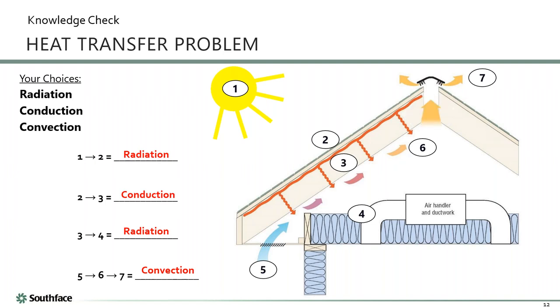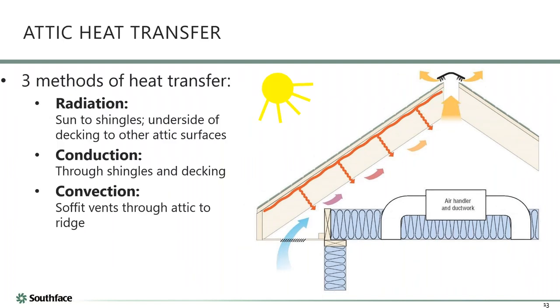We also talked about increasing convective cooling in an attic with a fan, but that's just spending money to treat the symptom — the air got hot — not addressing how heat got into the attic. No matter what, ducts are still in a hot space being radiated by hot surfaces, and the fan doesn't discriminate — it can pull the attic under negative pressure and actually draw lots of conditioned air up into the attic. So we really don't want to do that.